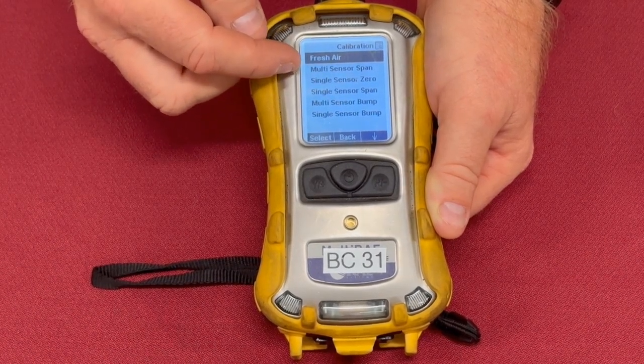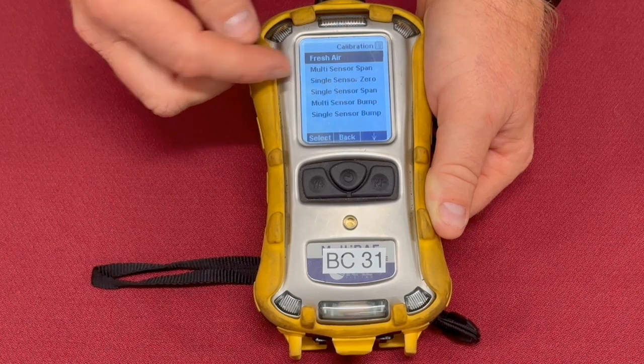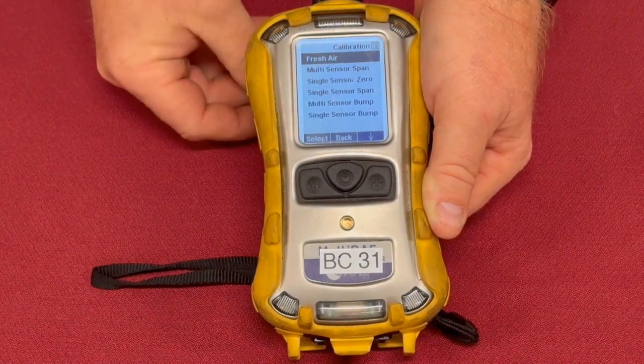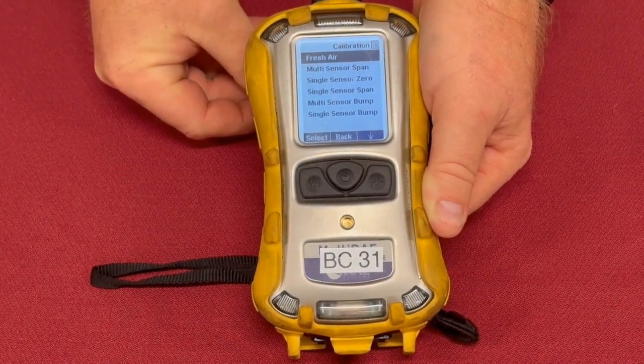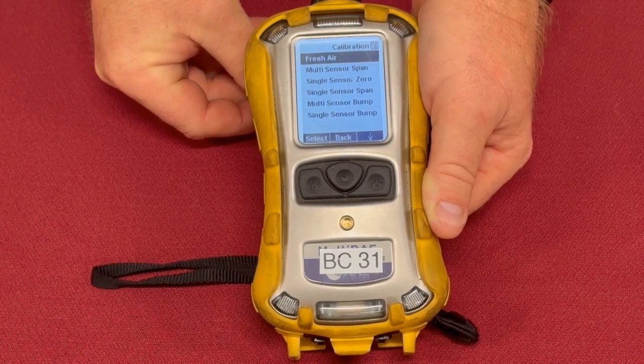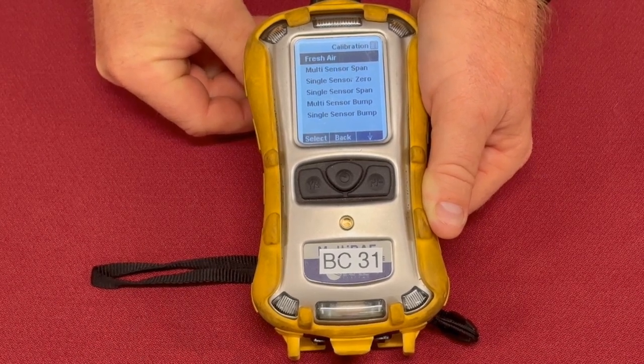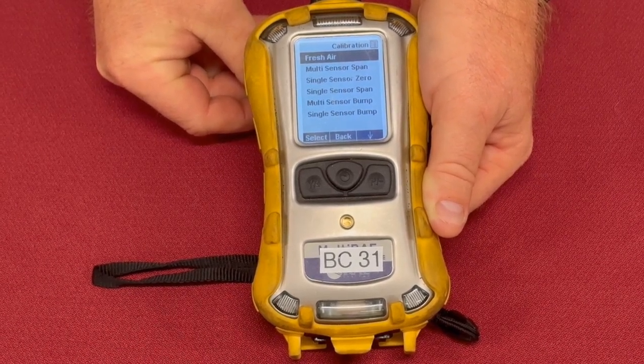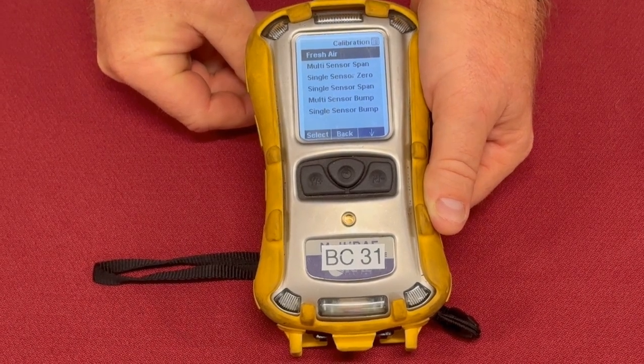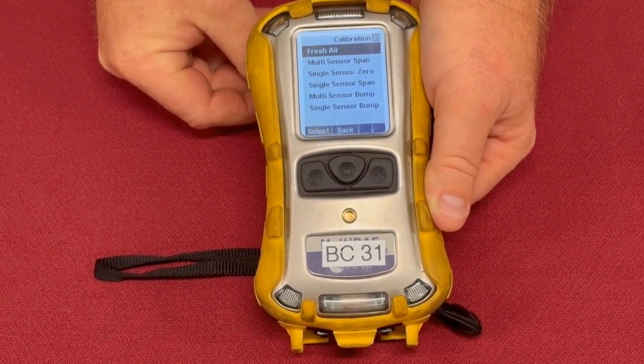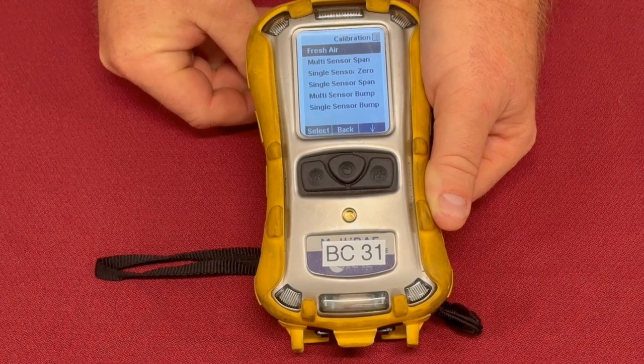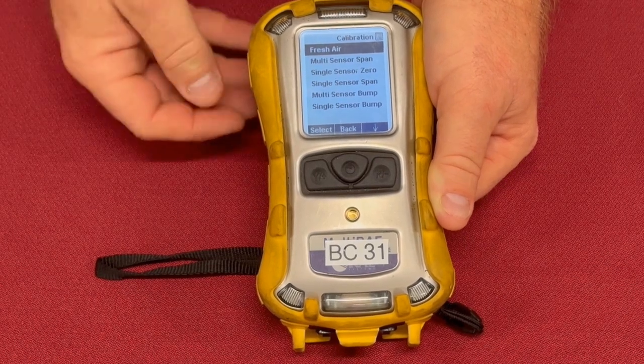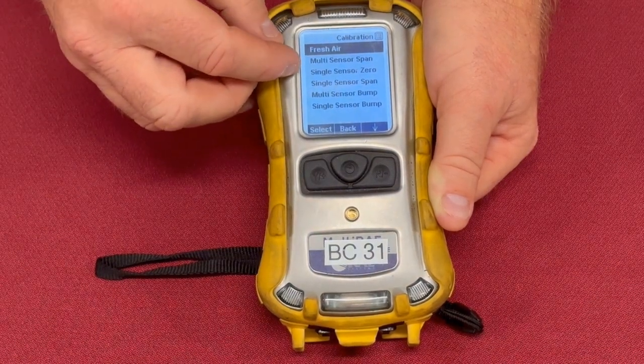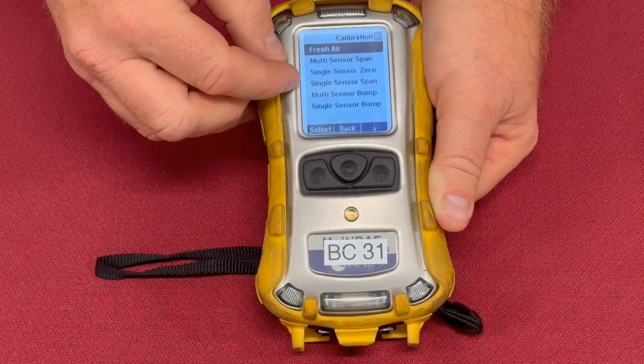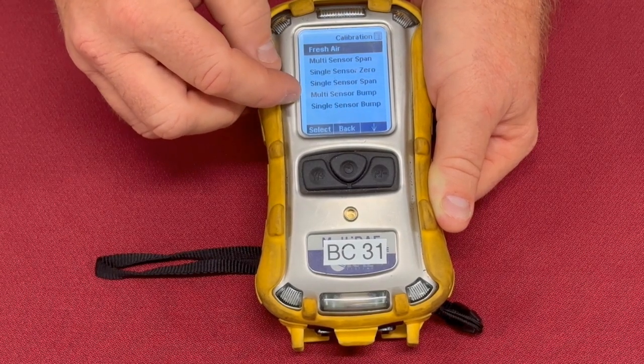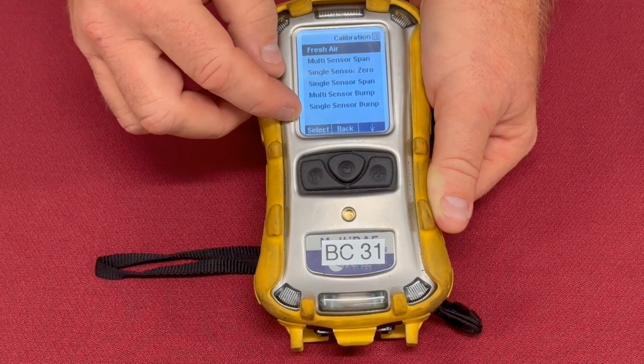Then it talks about a multi-sensor span, and you're like, okay, we haven't talked about span at all. What's a span? Well, in the meter world, span and calibration are exactly the same thing. Everywhere else in this meter, it's going to talk about calibration, except right here, it's going to call it a span. The other thing, you can do a single sensor 0, single sensor span, multi-sensor bump, or single sensor bump.